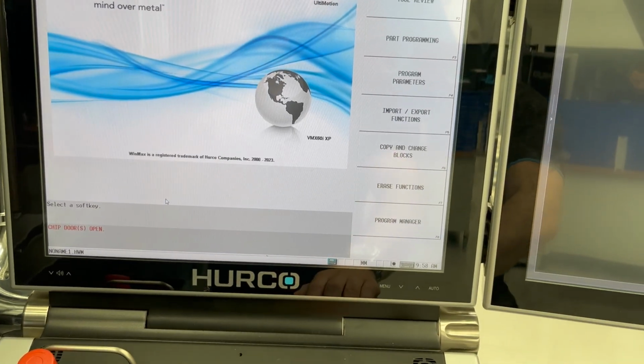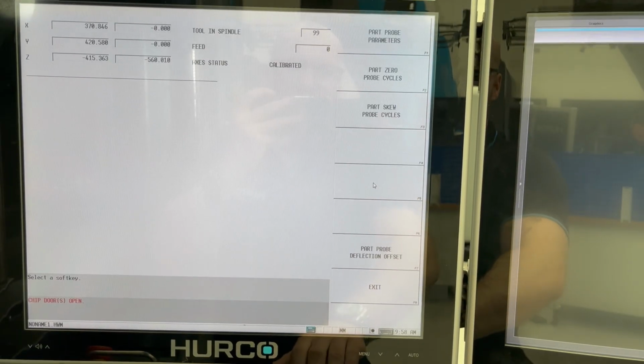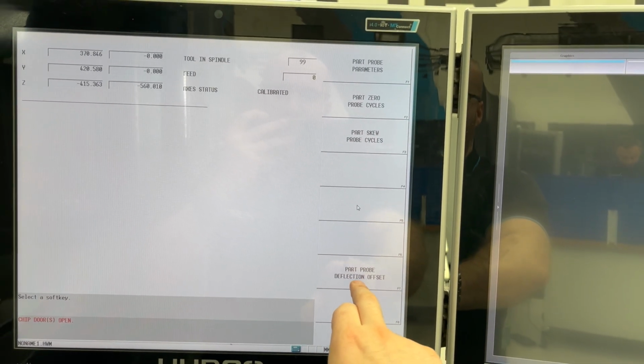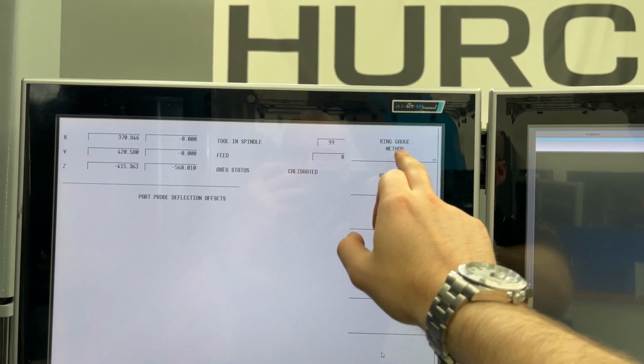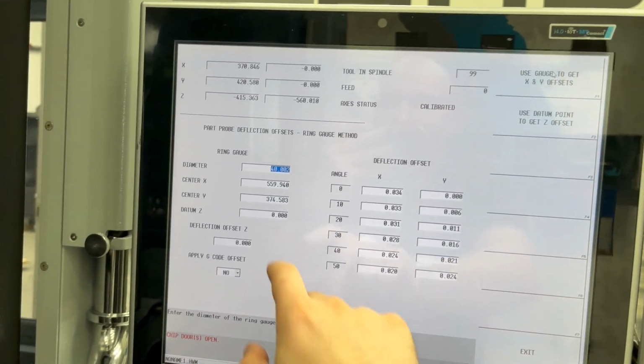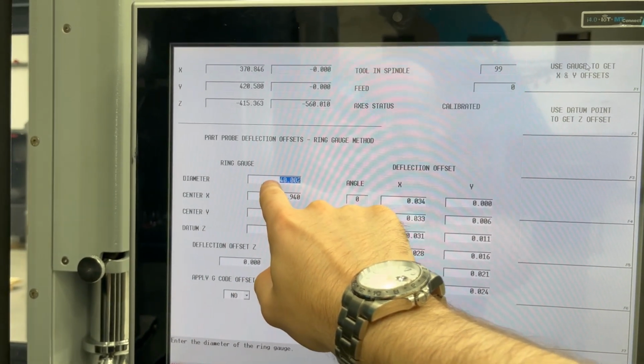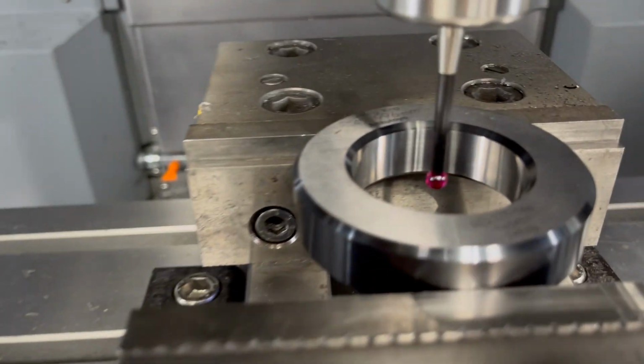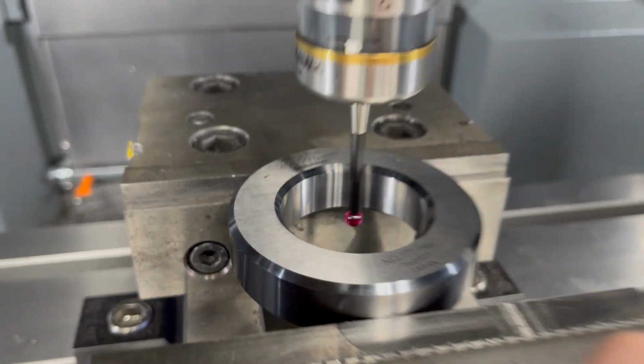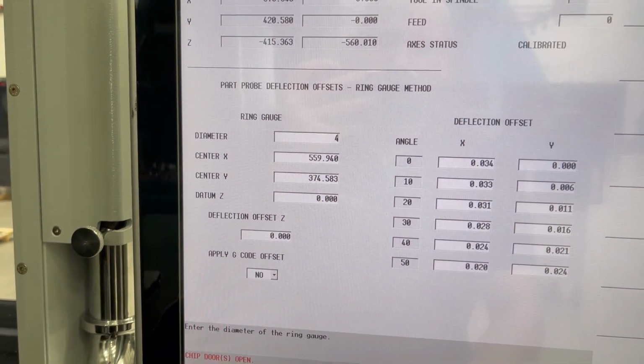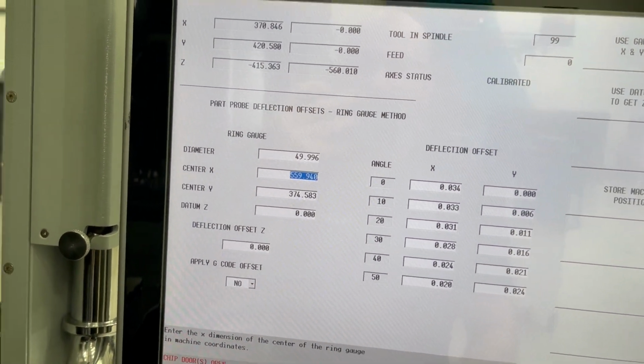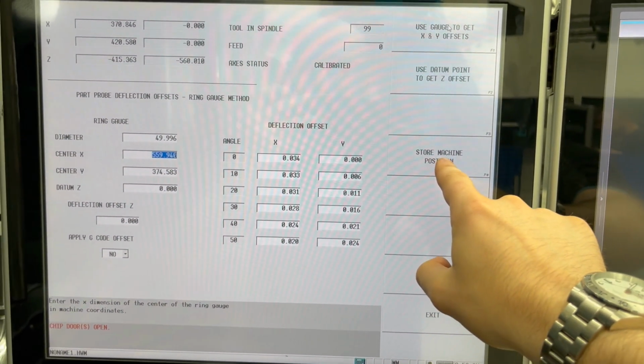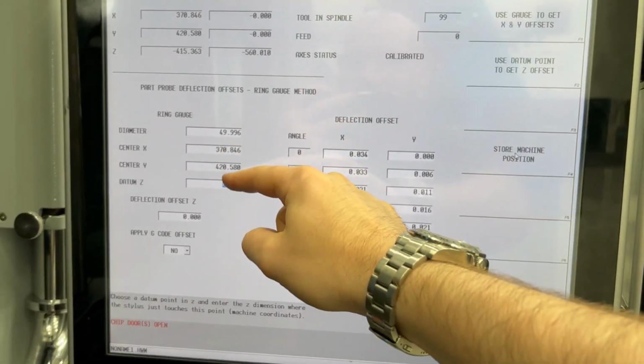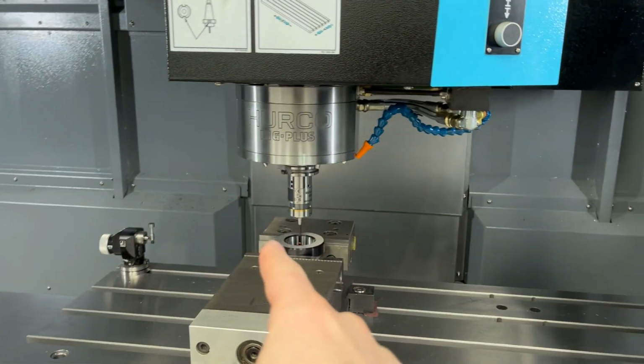Once you've got your part probe placed in the center of the ring gauge, go ahead and find the part probe deflection offsets page. At the top you'll see ring gauge method, and then you fill out all the details: the diameter of our ring gauge and where our 0 is, etc. As you can see, I've got a 49.996 diameter ring gauge, and then for the actual machine position where the part probe currently is, you want to type those into the X and Y center, or you can just hit store machine position and that will store those current positions into those two little tables.